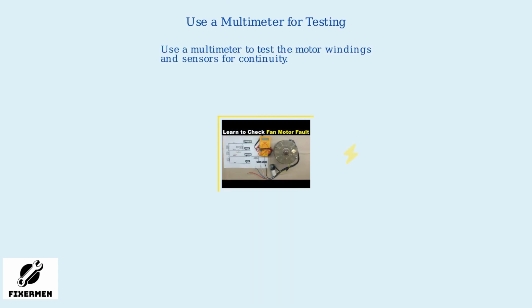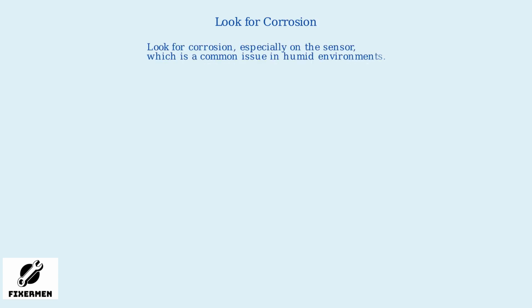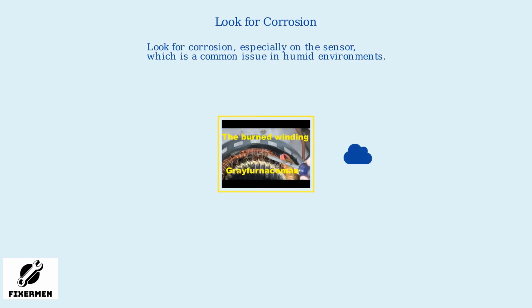Use a multimeter to test the motor windings and sensors for continuity. Set the multimeter to the continuity mode and check for proper electrical flow through the motor's internal components. A lack of continuity indicates a break in the circuit that needs repair. Look for corrosion, especially on the sensor, which is a common issue in humid environments. Corrosion can interfere with the sensor's ability to provide accurate feedback to the control board, triggering the H6 error. Clean or replace corroded components as needed.